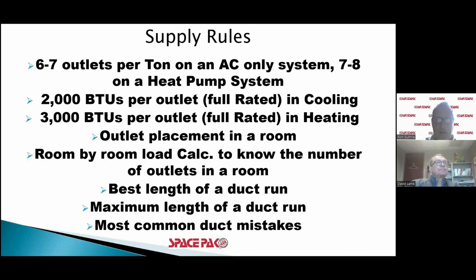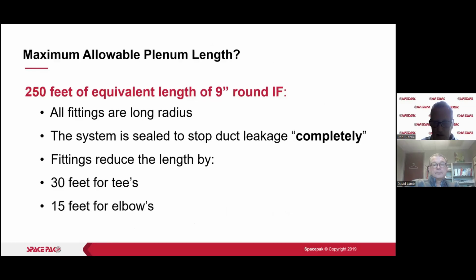All right, outlet placement in a room. We could talk about that. It's kind of the same common sense that we would have in a conventional system too. We don't want to put it over where somebody sits, over grandma's rocking chair, over a bed, over a curtain or something else that's going to move around. So common sense there. All right, we do need to do a room by room load calc. Otherwise, we don't know how many outlets to put in a room. And that relates directly to this 2,000 and 3,000 BTUs per full outlet. And we'll talk about full outlets as well. All right, we'll talk about the best length of a duct run, maximum length of a duct run, and most common duct mistakes.